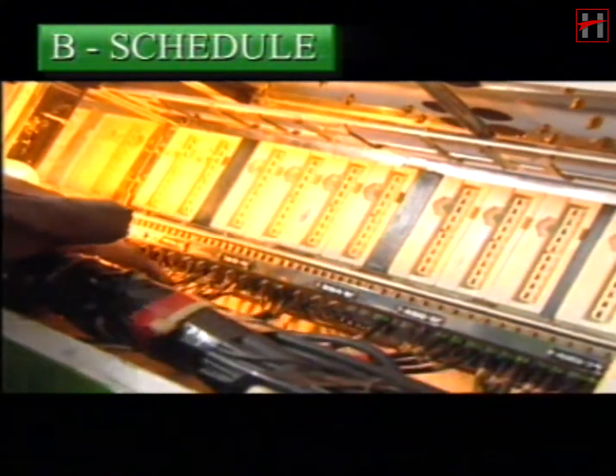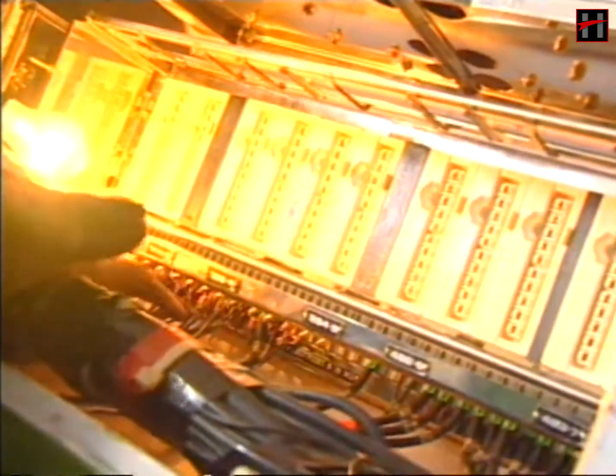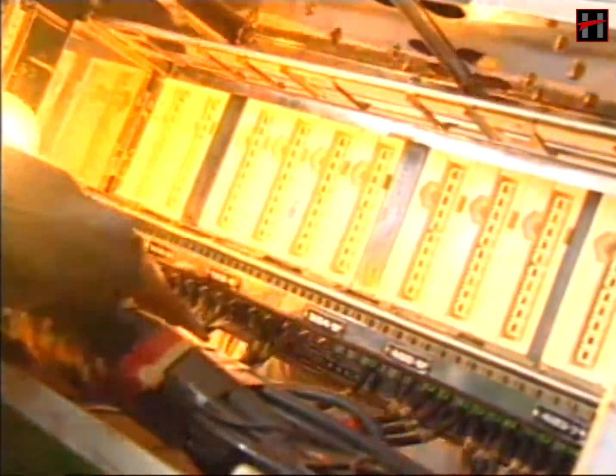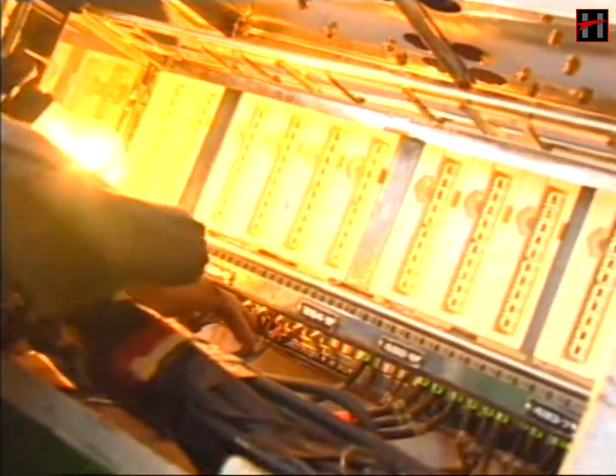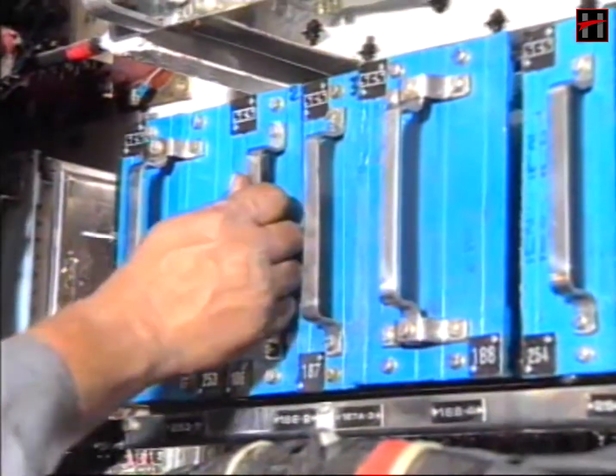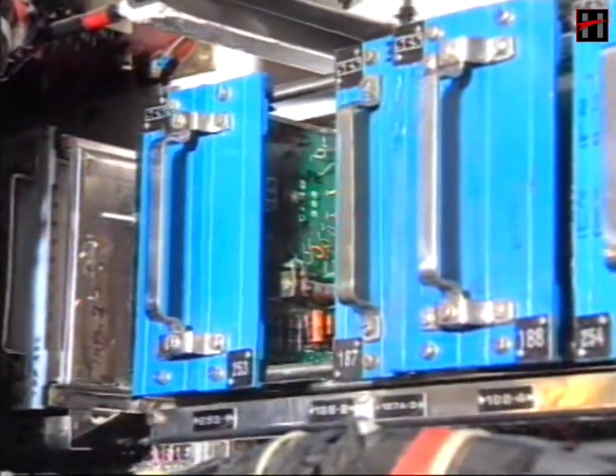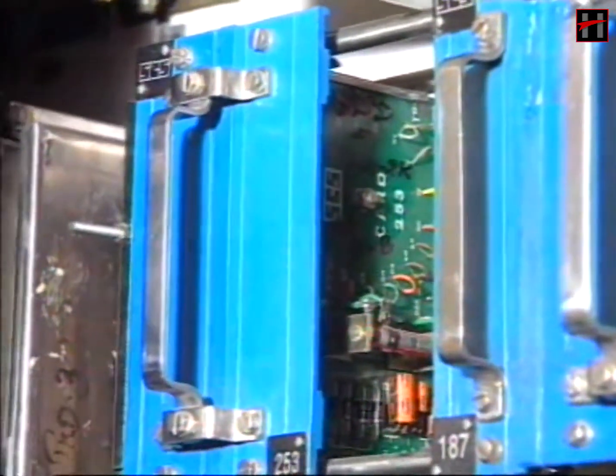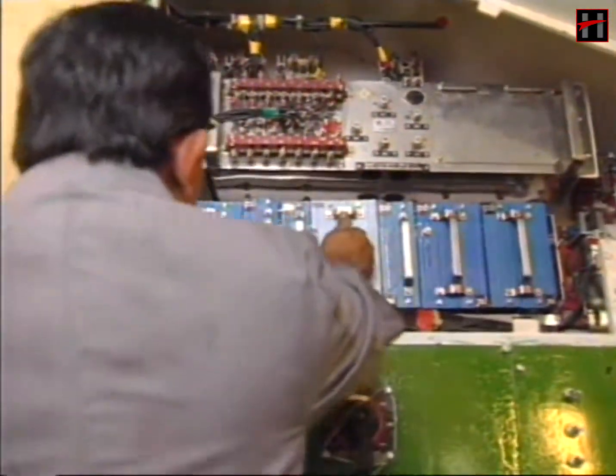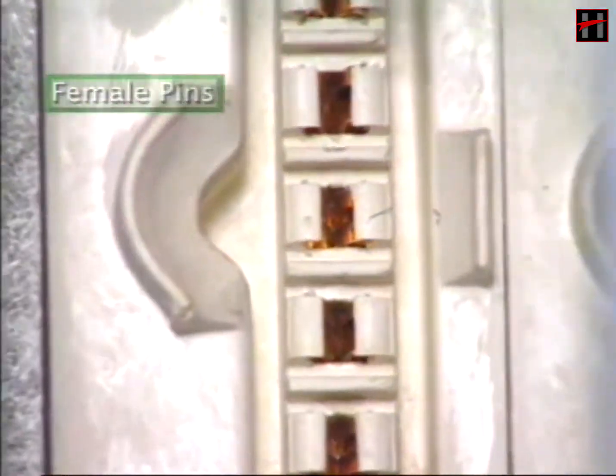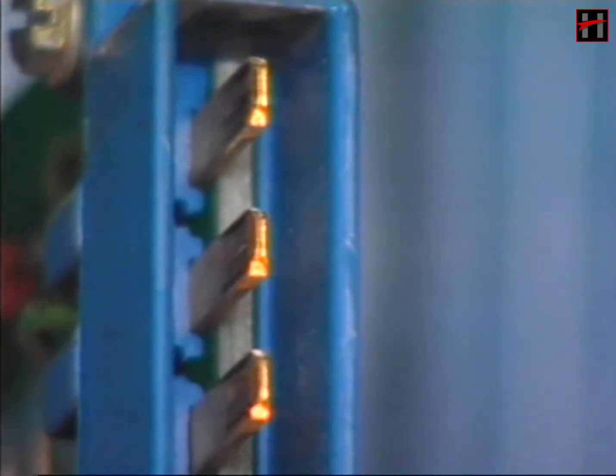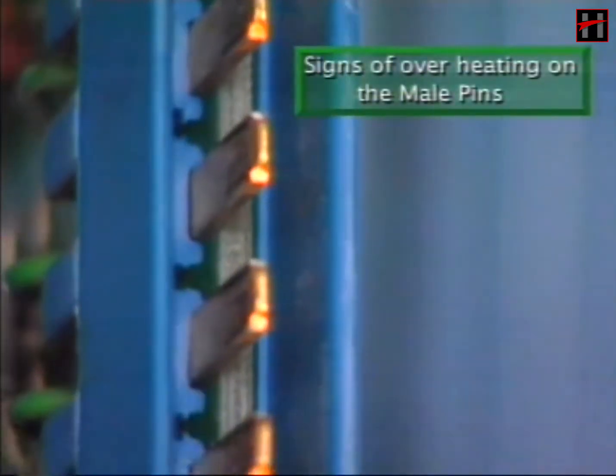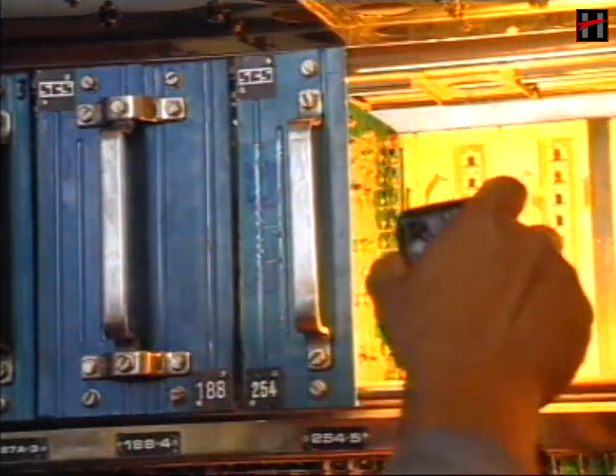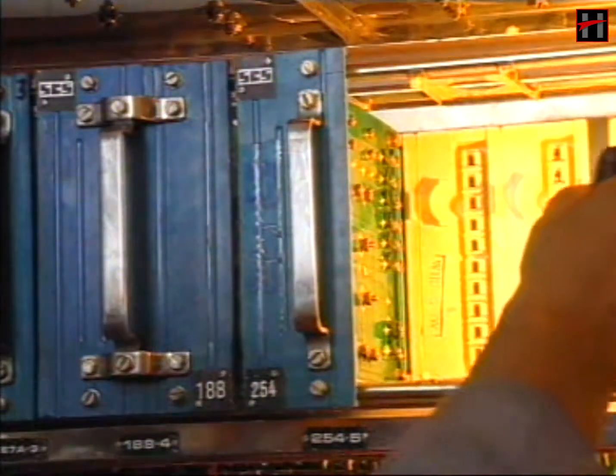In the B schedule, all the items that were visually checked in the A schedule should be physically checked in the B schedule. In addition, take out all the cards of the excitation panel, voltage regulator panel and the TRP from their sockets and check the female pins and their corresponding male pins. If any signs of overheating is observed on the male pin, clean the flash marks with lintless cloth or emery paper. If any signs of overheating is observed on the female pin, change the card.